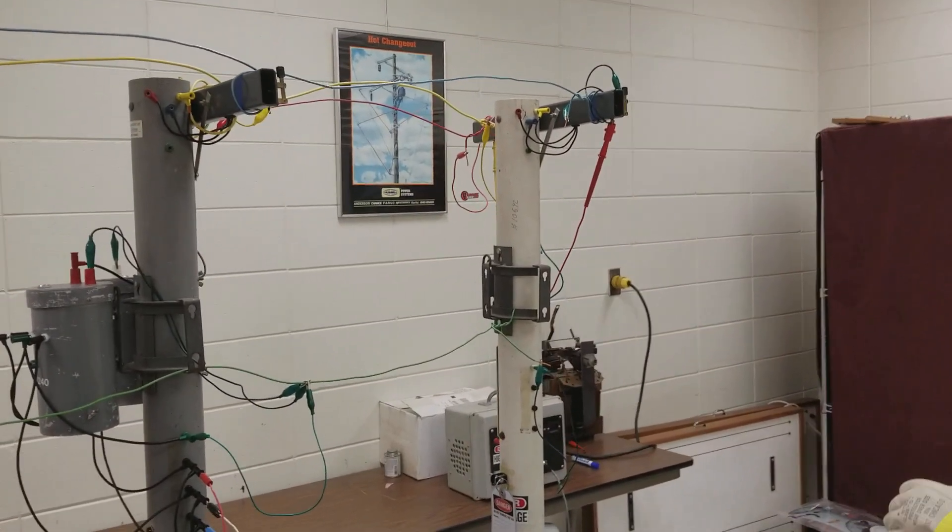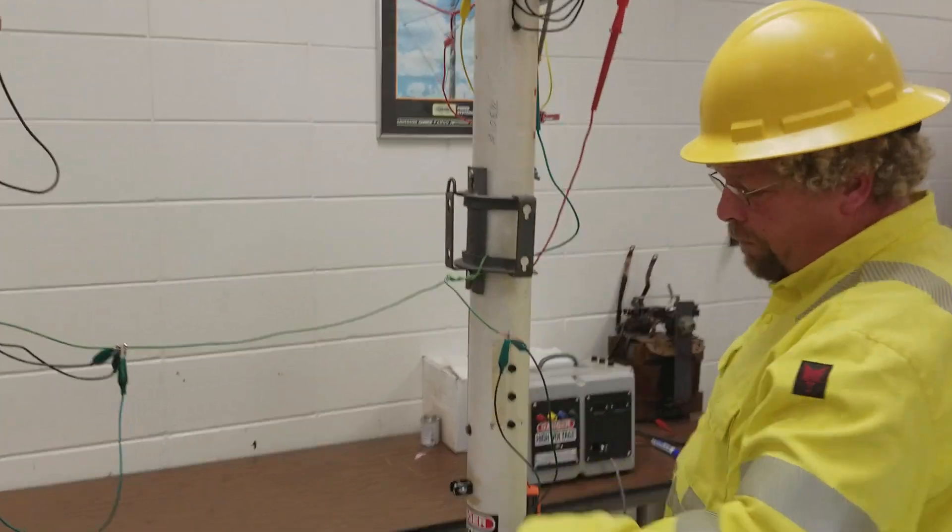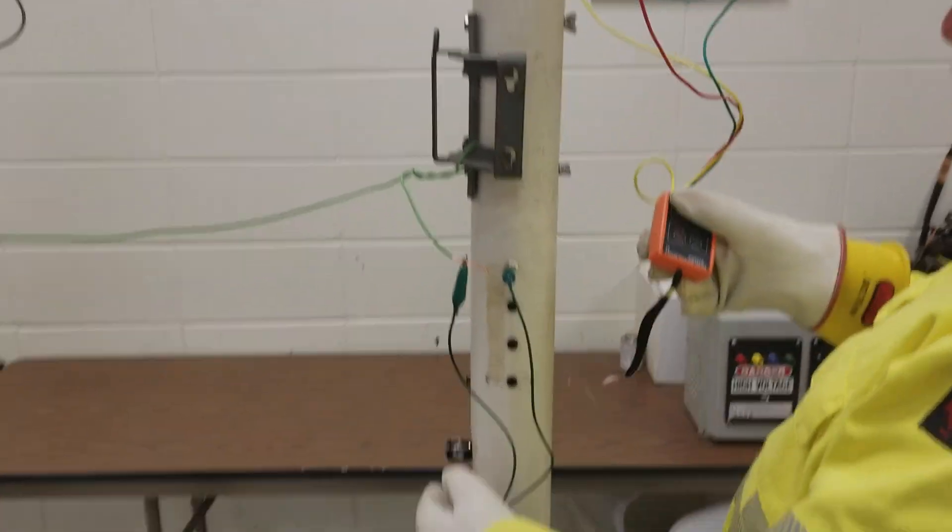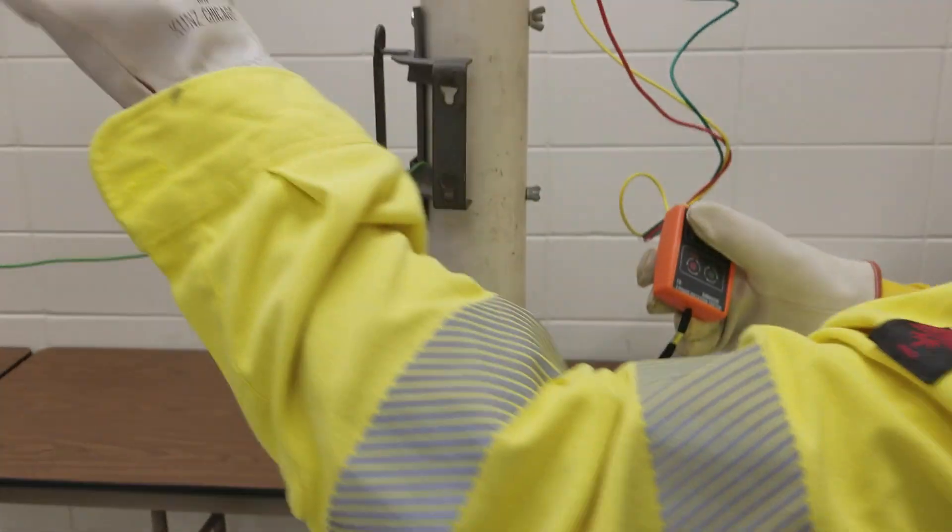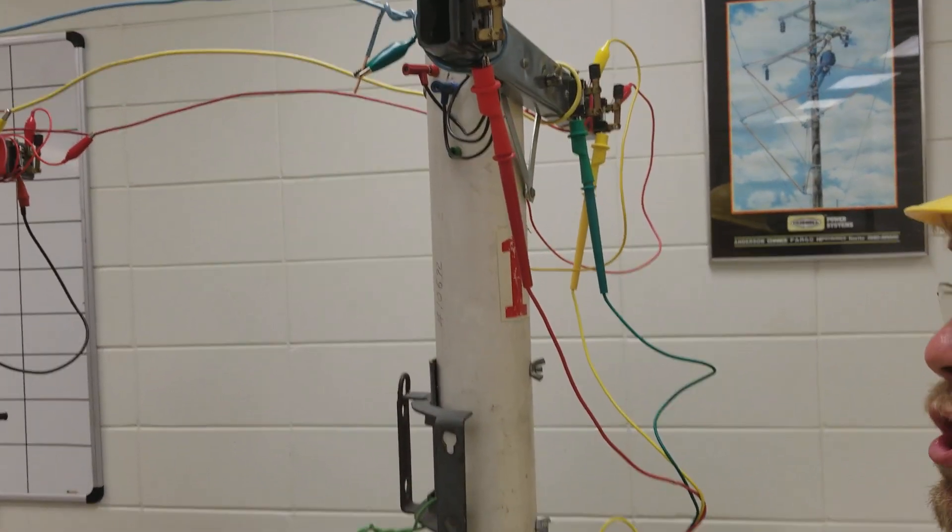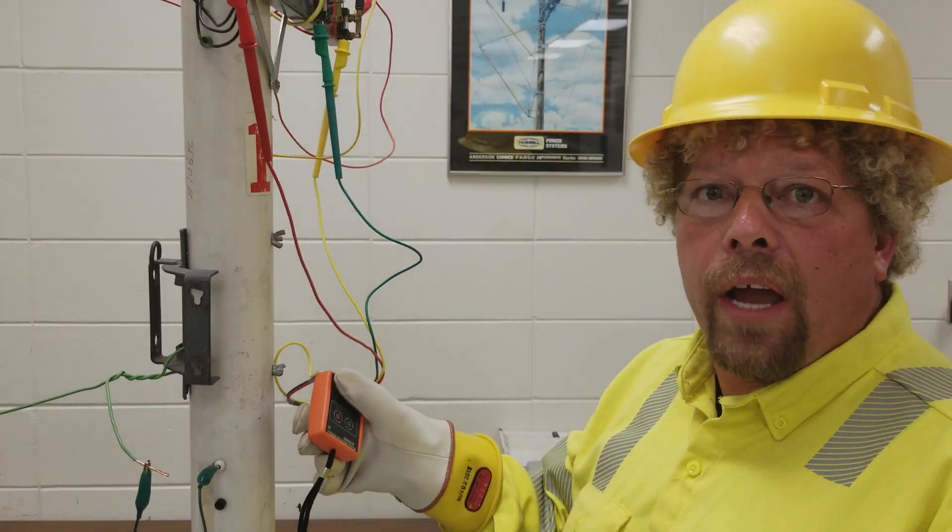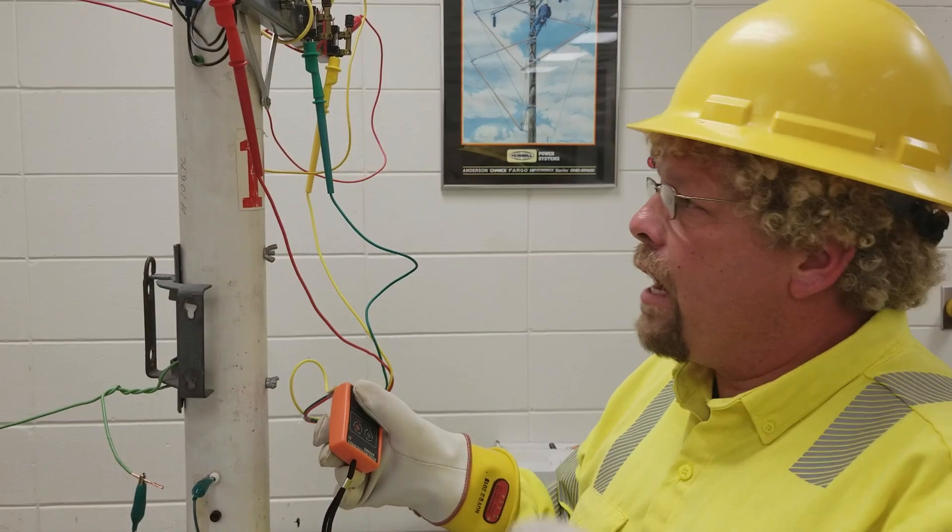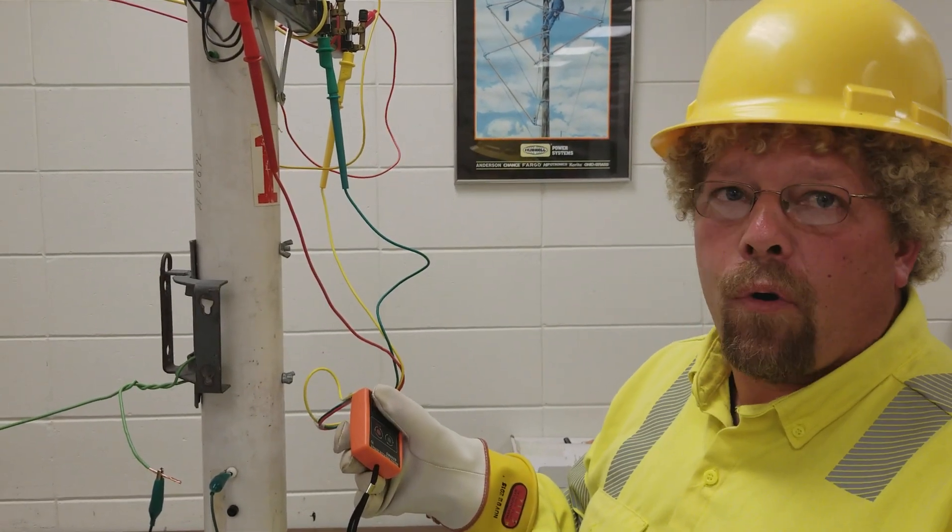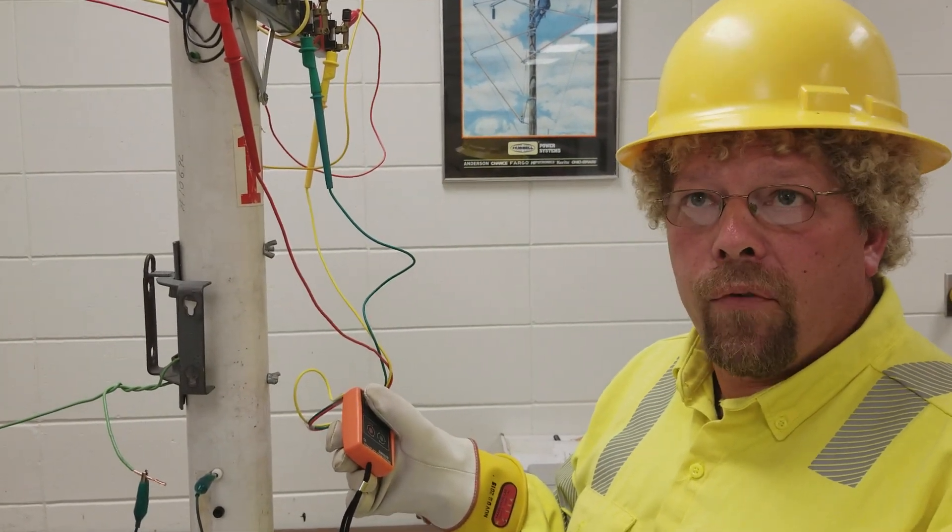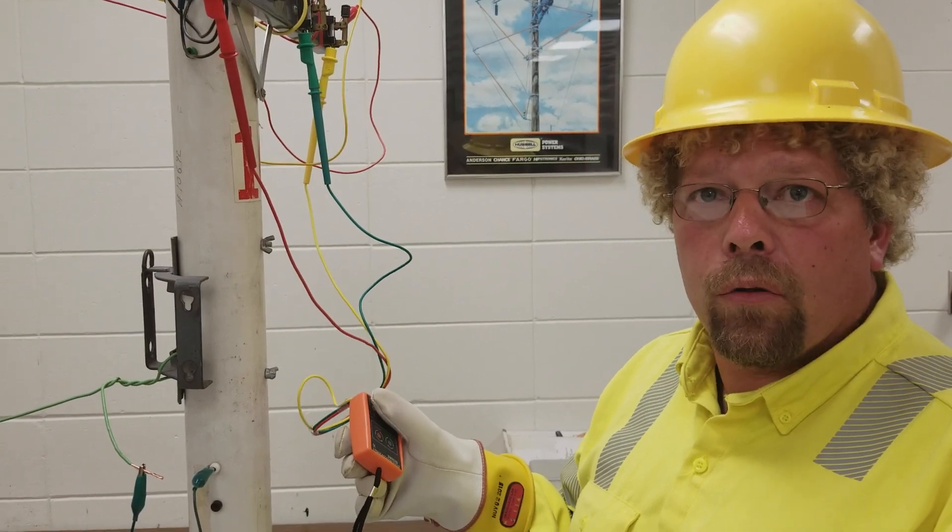So what we're going to do first, we're going to energize the system. So this rotation meter is hooked up to the primary. By the way, these transformers are actual transformers. There's a primary and a secondary winding in the transformers. And the voltage that comes out of these transformers is real, 120, 240 with a 208 volt wild leg.